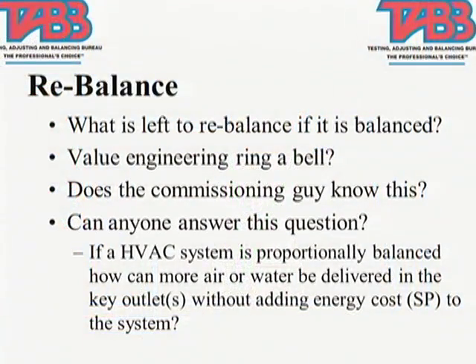If an HVAC system is proportionally balanced, how can more air or water be delivered to the key outlets without adding energy costs to the system? I'm not aware of any way to do it without changing the system. You cannot deliver more unless you increase the static pressure. You can take static pressure off by replacing and resizing the duct or changing the system, but otherwise it's only going to cost more energy.